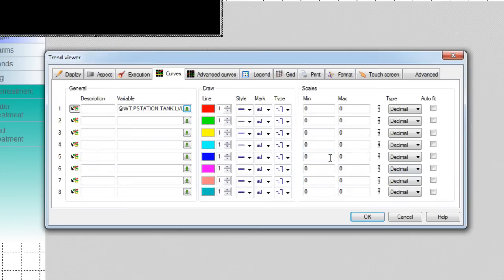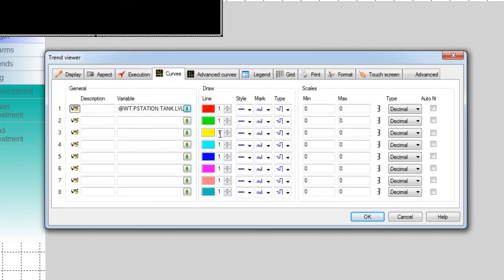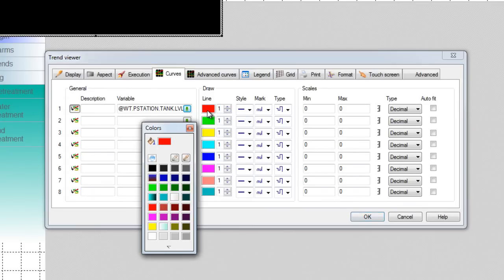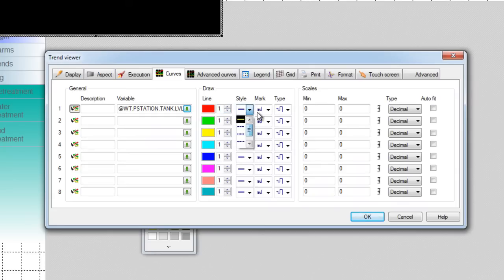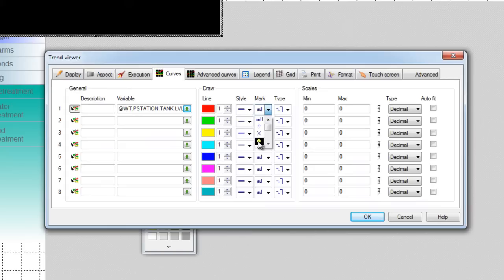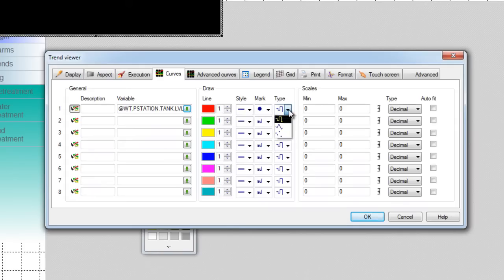If the variable has been configured to be archived as a trend, as discussed in the tutorial's Archives Basics, you will be able to display the historical trend for this variable. You can then modify the appearance of the corresponding trace with the color, the thickness, different styles, and a specific marker like this one. And you can also select one of the three types of trace. Here we select the single line type.